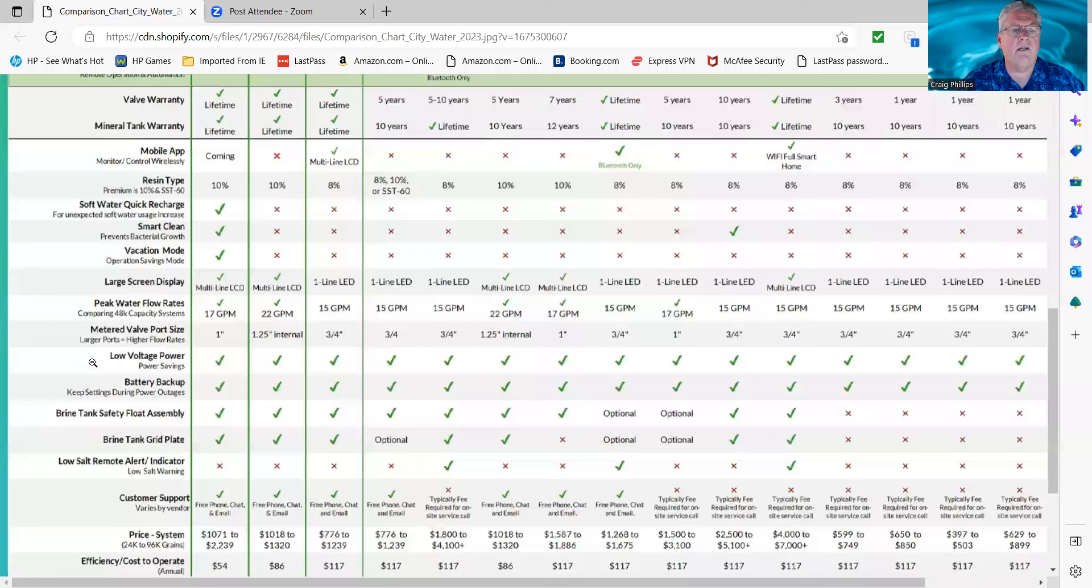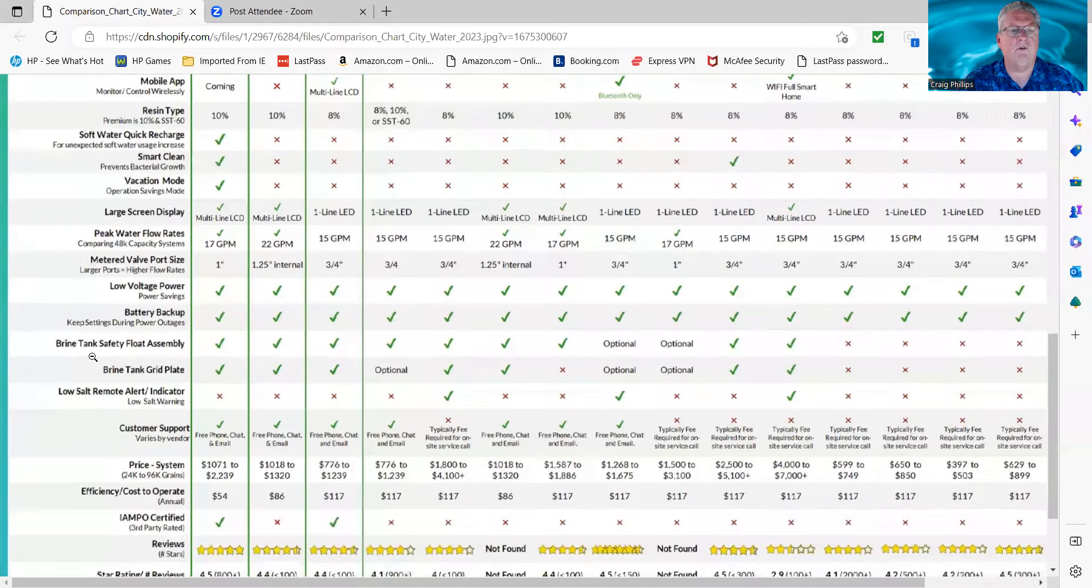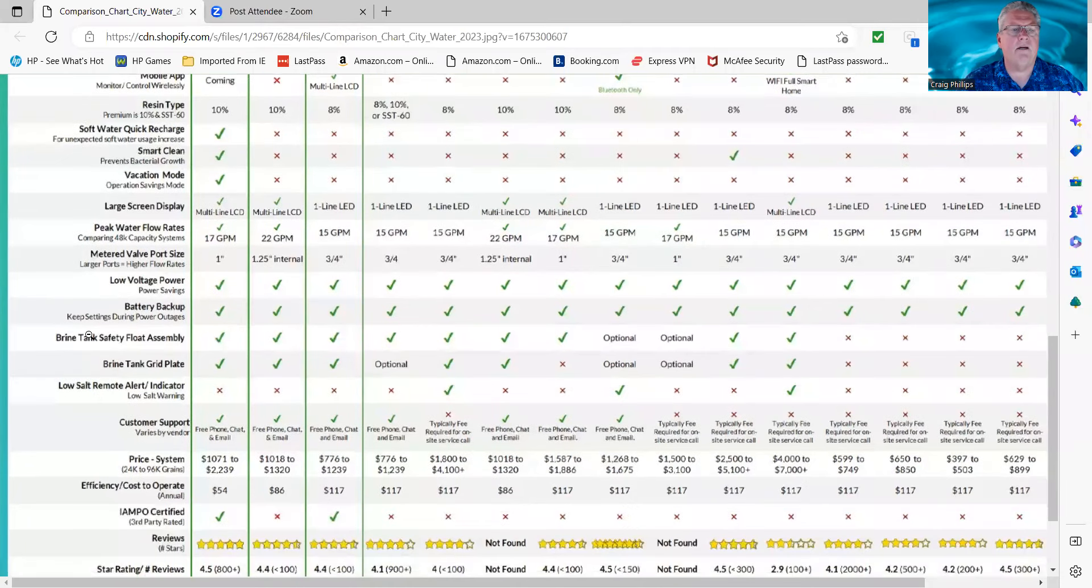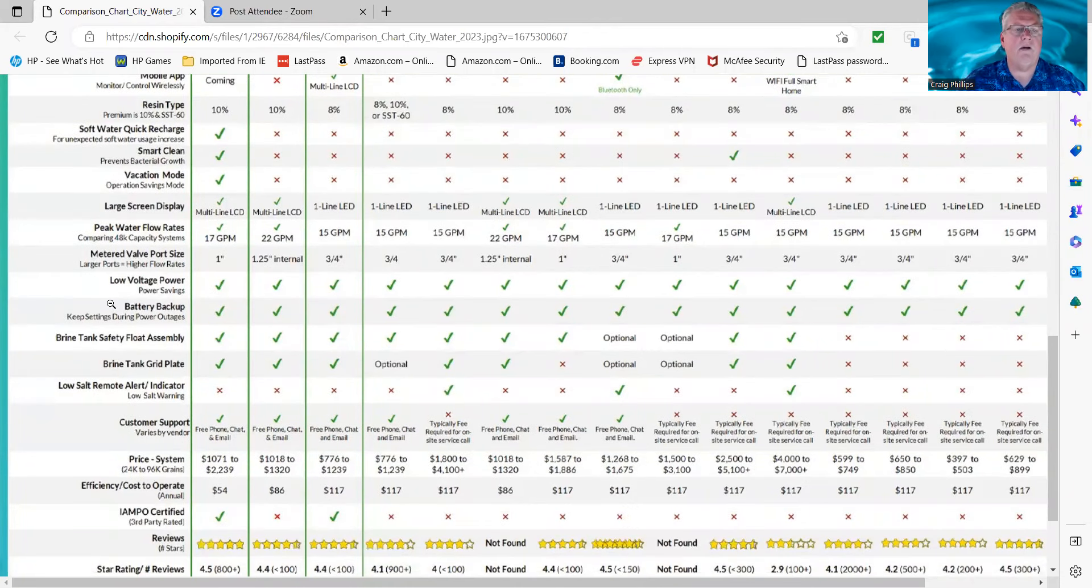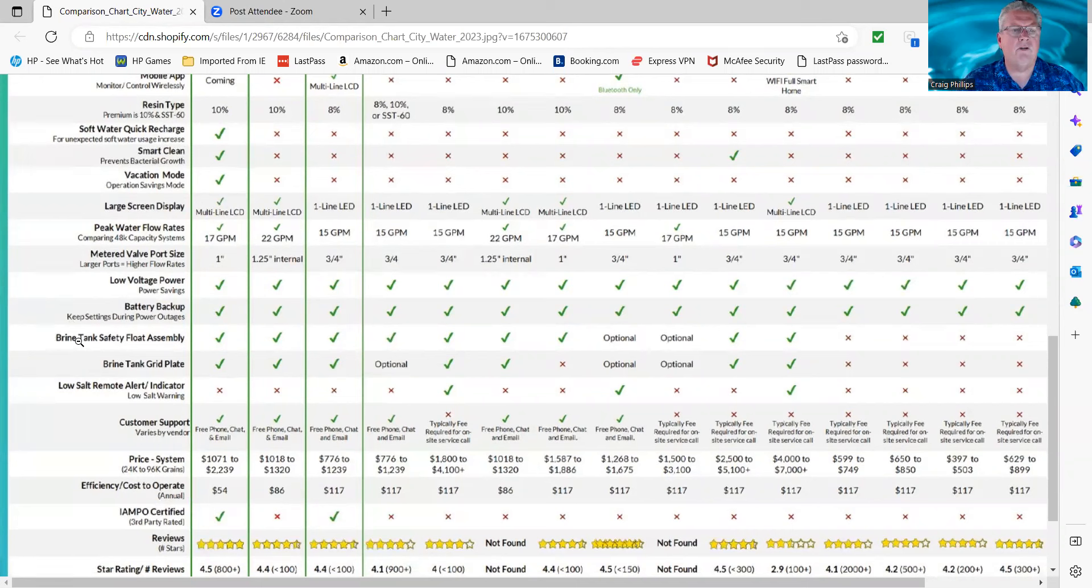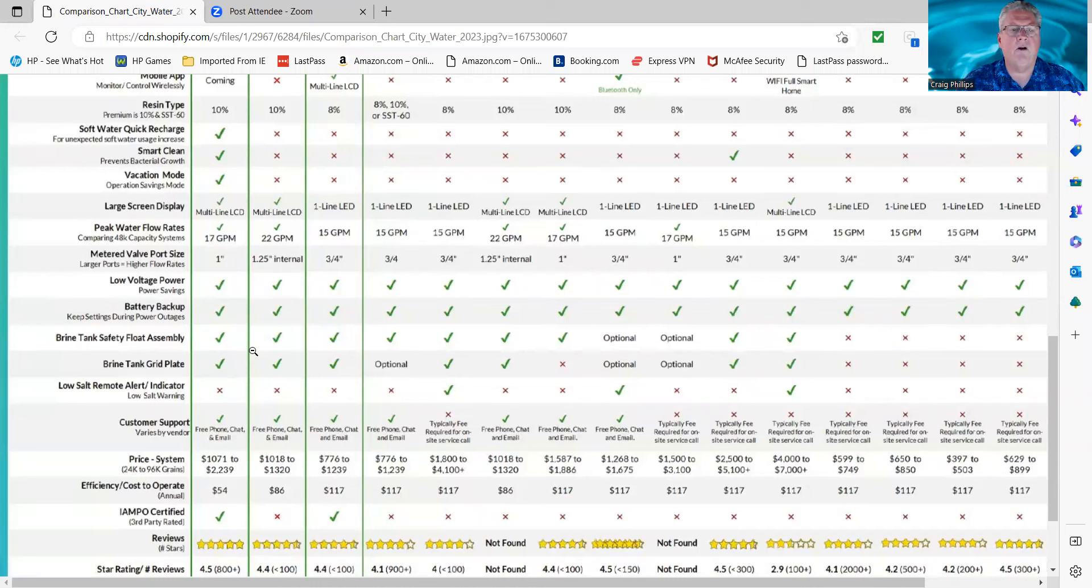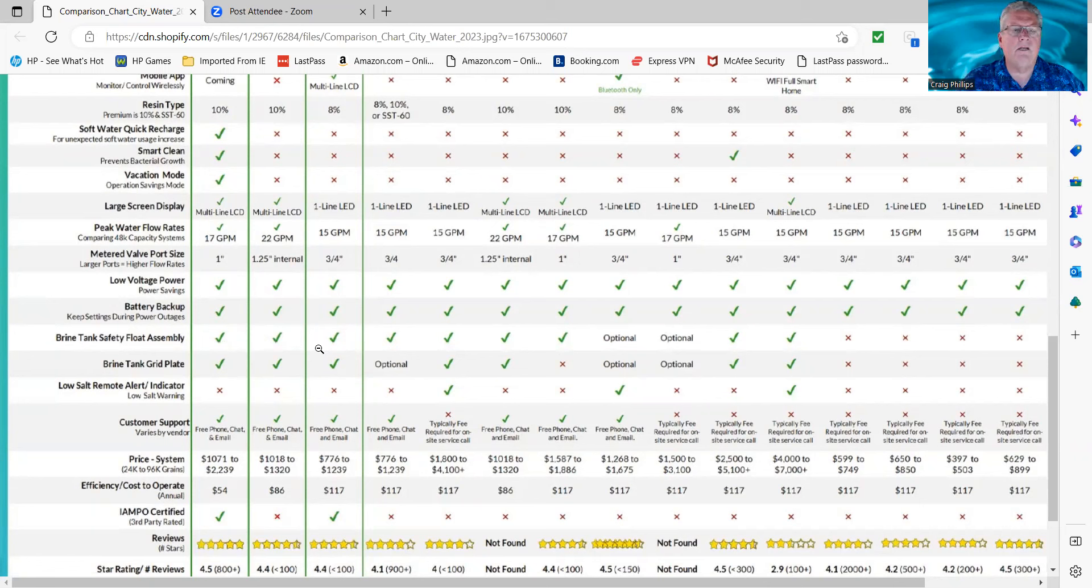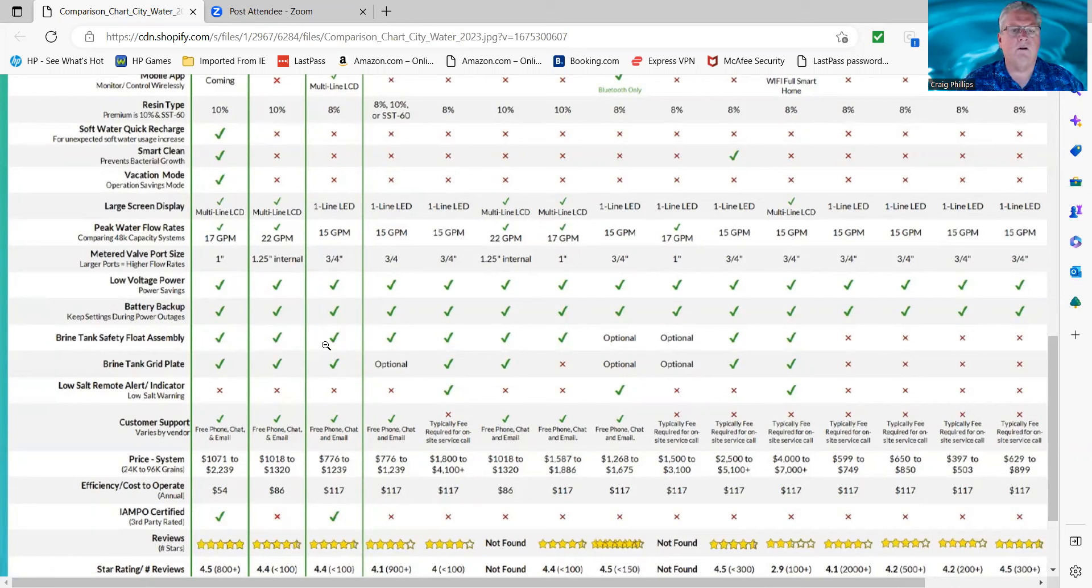Low voltage power, they all have it nowadays because they're all digital. So they're 12 to 24 volts. They all have backup batteries, so you don't lose your programming for a certain amount of time if power goes out. Brine safety float is for the brine tank that holds the salt. That's pretty important. If your injectors get plugged on your control valve or if you have a restriction in your drain line, the system will be able to put water in the brine tank and it won't be able to pull it out. So if that happens, if you don't have a safety float, water can basically go all over your floor and create a salty water mess for you.